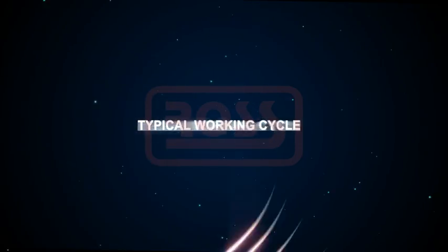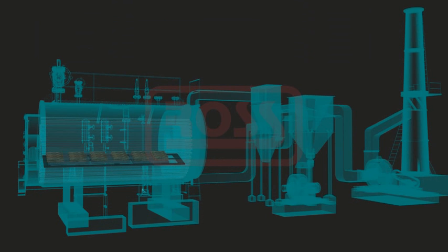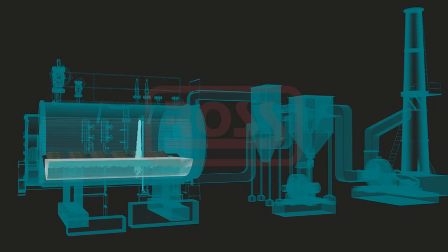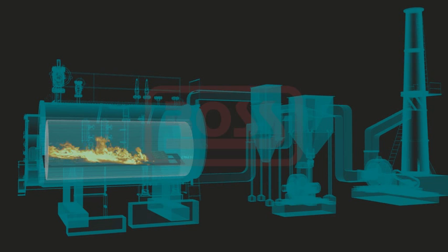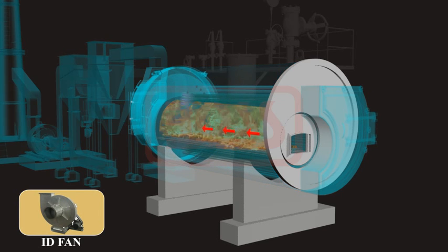Typical working cycle: Soft feed water is first filled in the boiler shell by starting the feed water pump. Normal boiler level is maintained automatically. Fuel bed prepared on the grate bars is then ignited manually. An ID fan is started to provide necessary air draft for combustion.